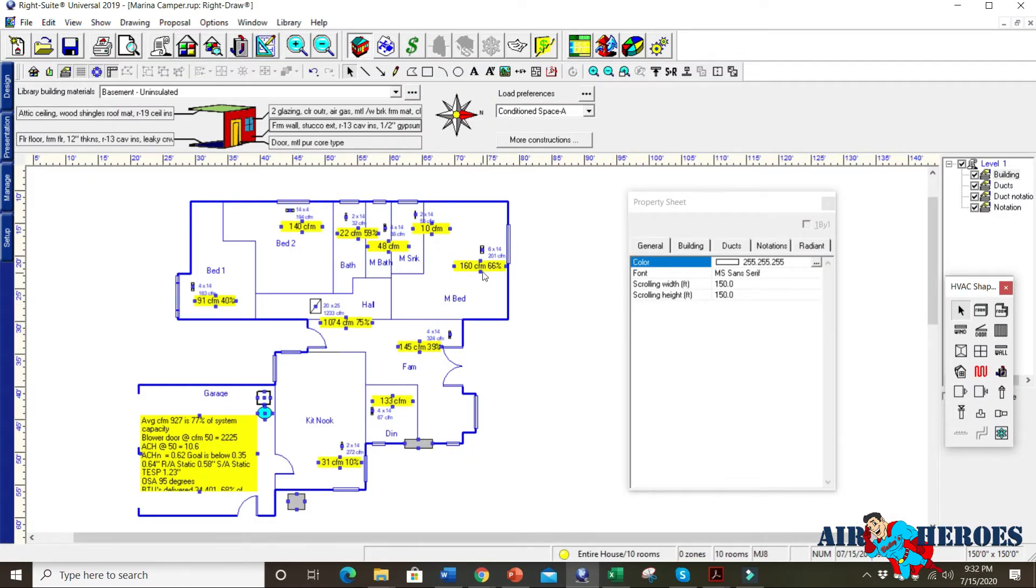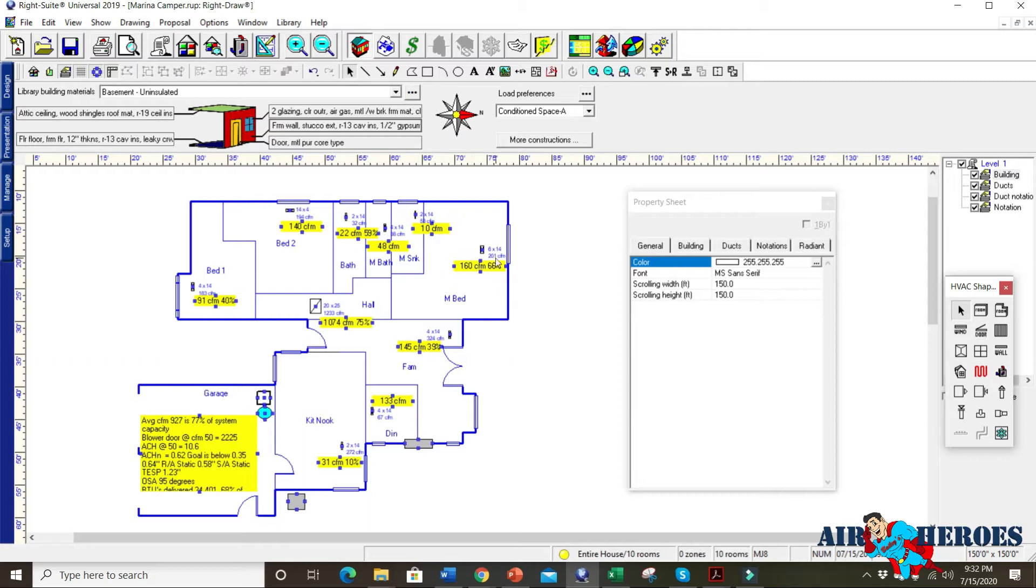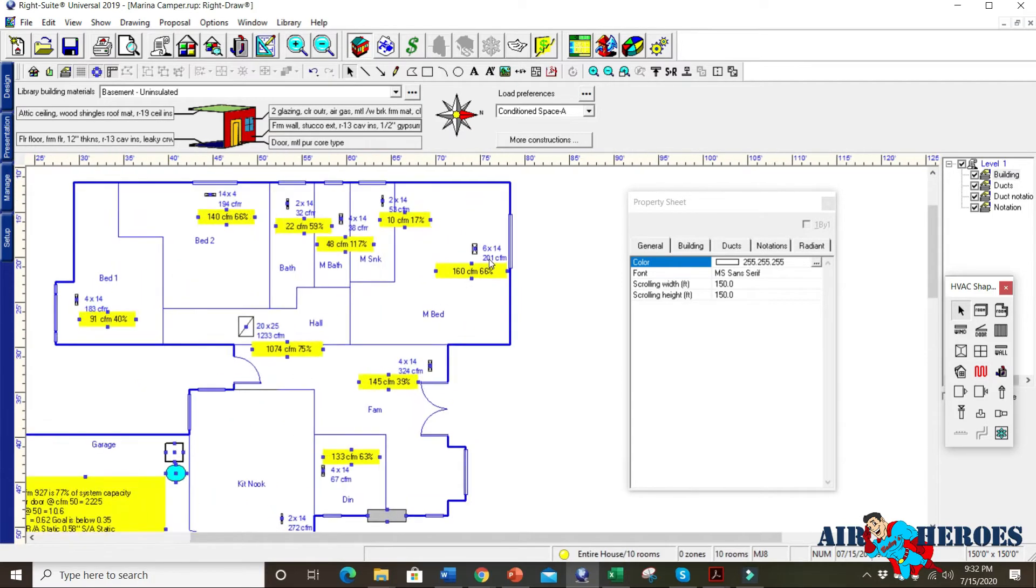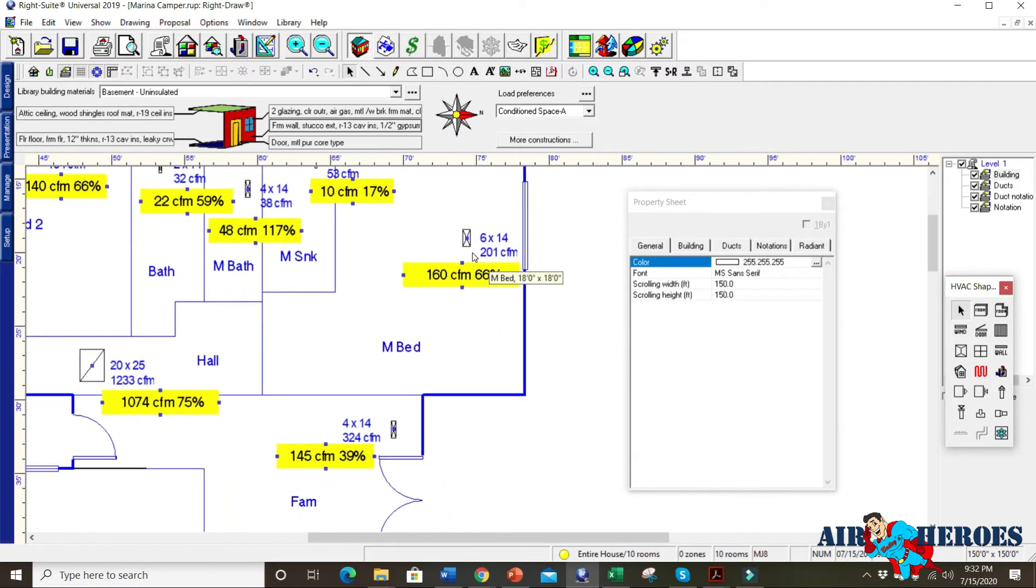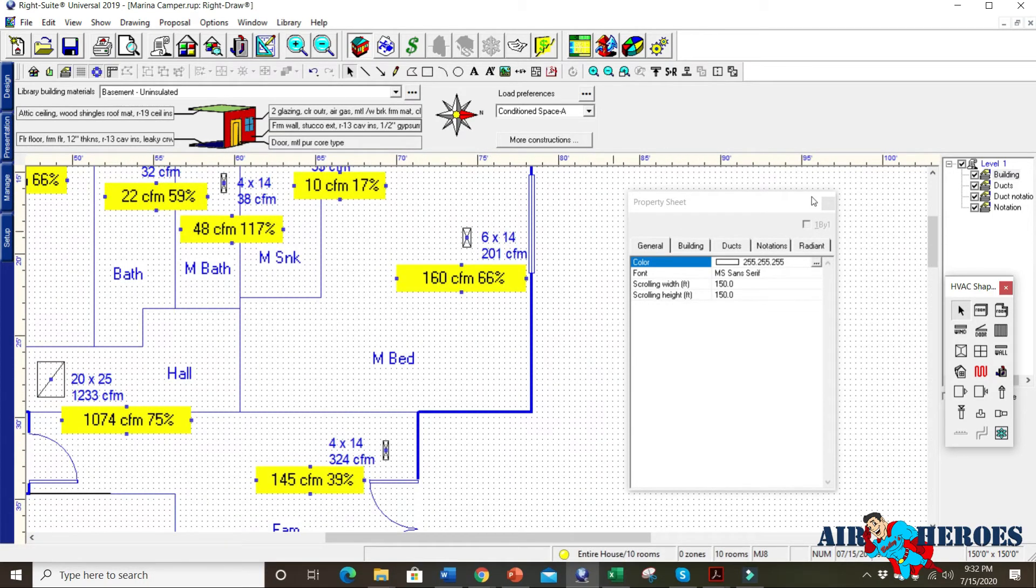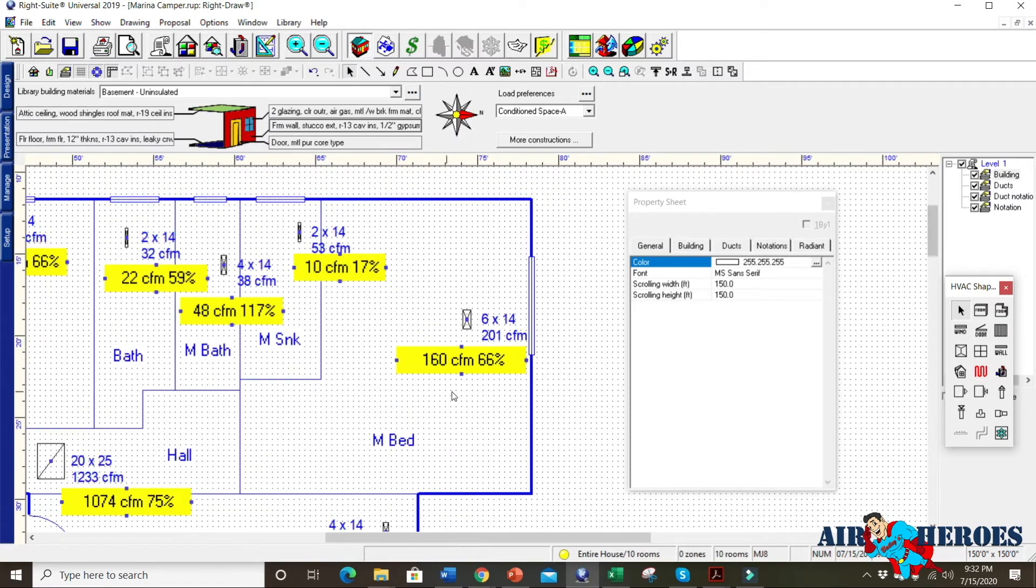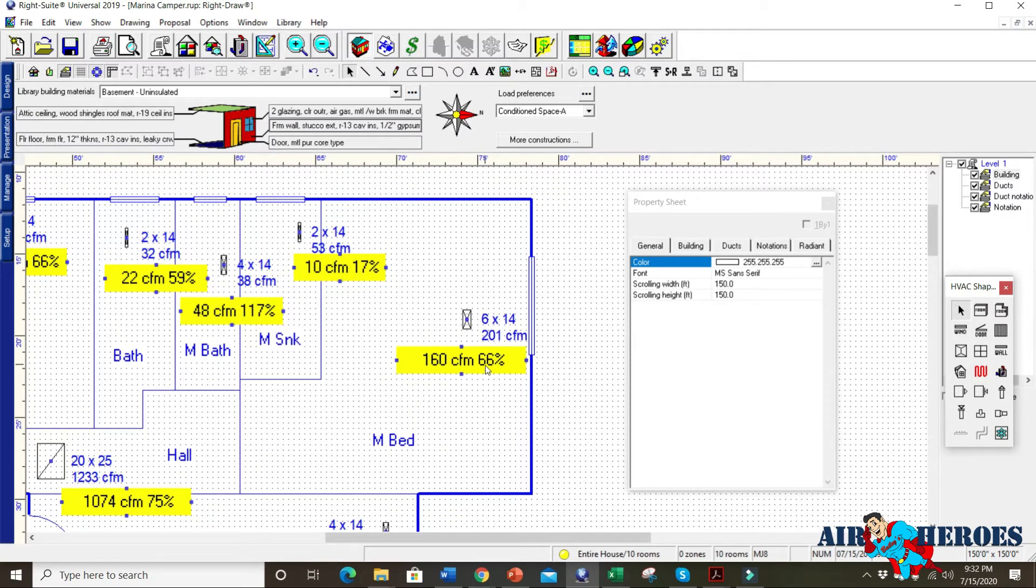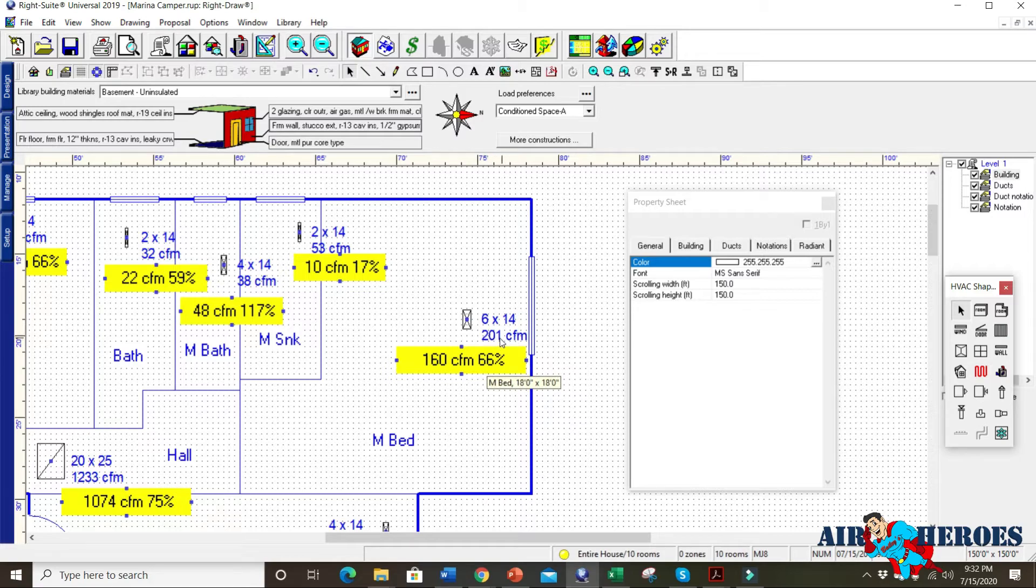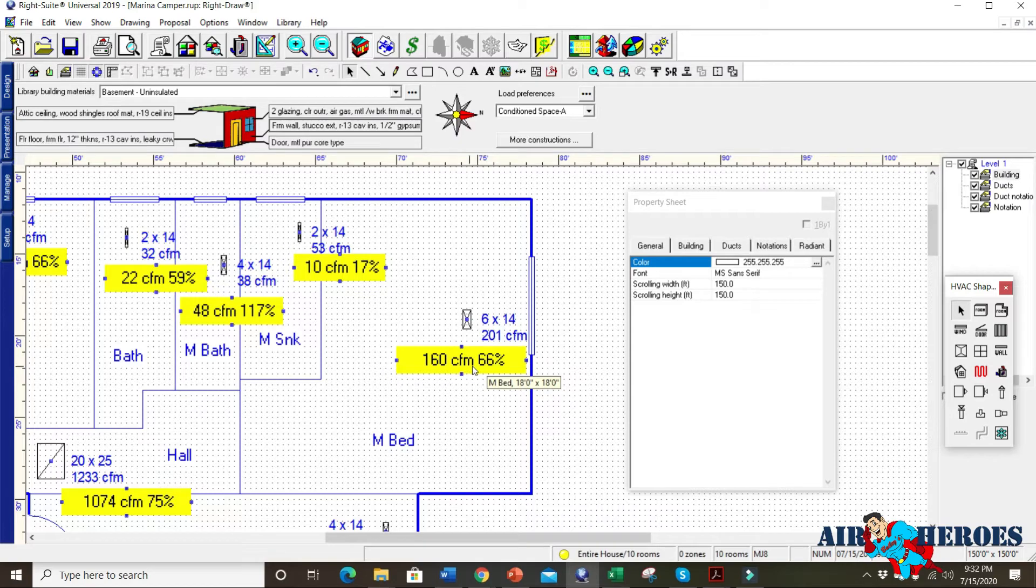So we go back to the drawing screen here. We can see that these yellow tags are what we measured when we do a test in and what's in the blue, that's a register in the blue is the CFM that it's supposed to be. So let's zoom in. I like this one. So this is the reason Wrightsoft works so well when you do a load calculation. So according to this, we measured 160 CFM. It's supposed to be 201 CFM and we're at 66% of that.